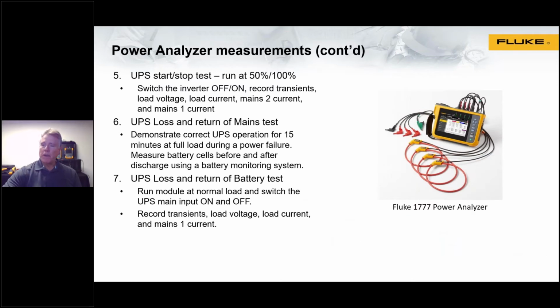Our next test is a UPS start and stop test. Really what you're looking for is correct operation when the UPS is switched on and off with full load, and you'll do this at both 50% as well as 100% load. So the process is, while recording or looking for transients with a power analyzer, you would be looking at load voltage, load current, and then the mains 2 and mains 1 currents.